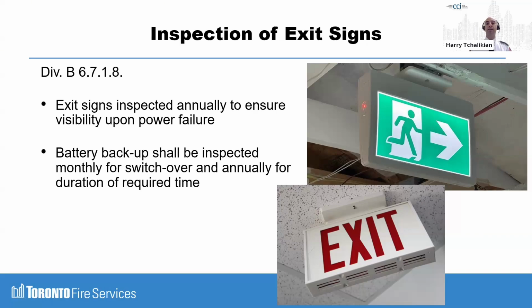It was separated from the regular emergency power testing, and the exit signs are now addressed separately. So it's what the inspector would look for in the test records. Make sure your emergency lighting and your exit signs are two separate records. That is new, even though the testing of the exit signs was always required.